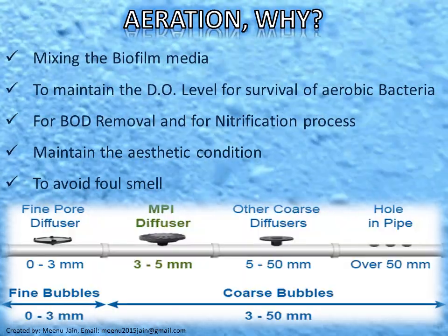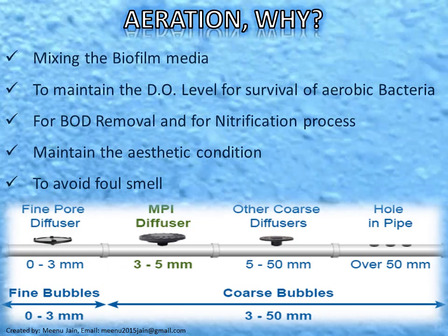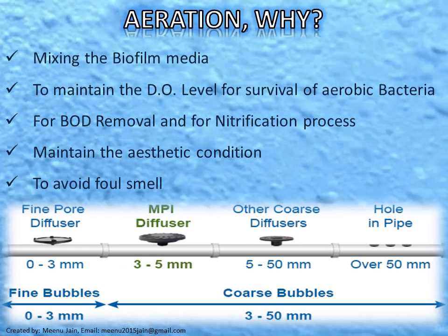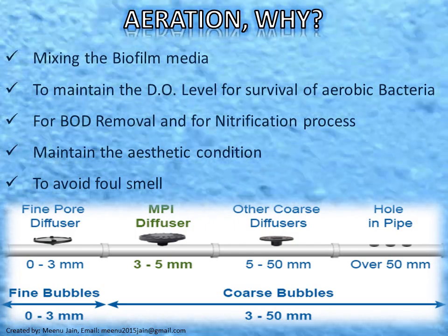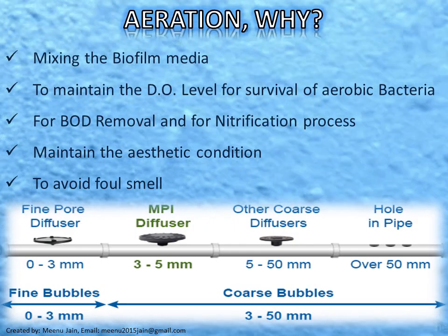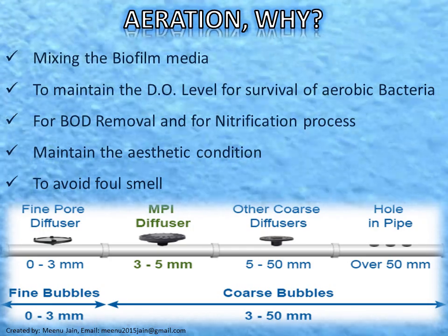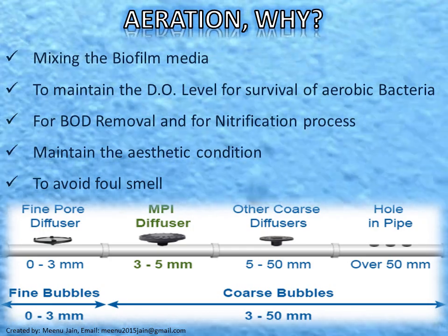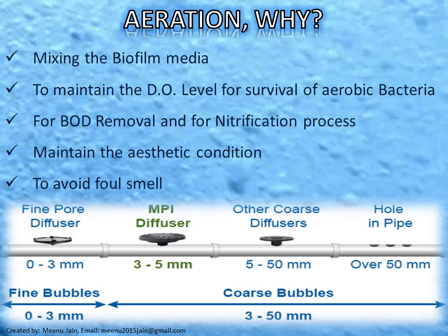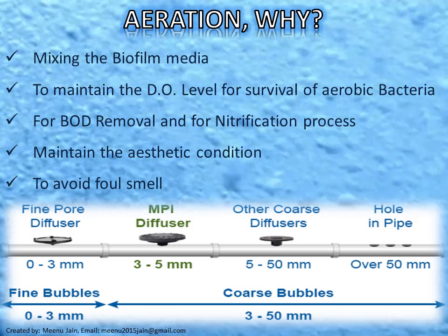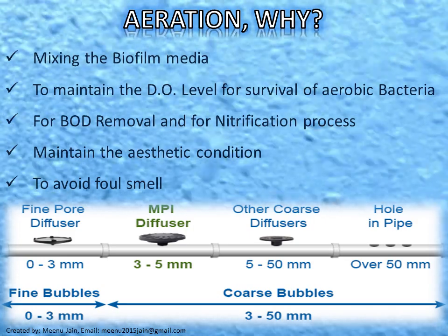Before going into much detail about submerged aeration, the first question is: what is the need for aeration? In an MBBR tank, aeration is required for mixing the biofilm media, to maintain the DO level, and to provide complete aerobic conditions for survival of aerobic bacteria for BOD removal and the nitrification process, and also for maintaining aesthetic conditions and avoiding foul smell.